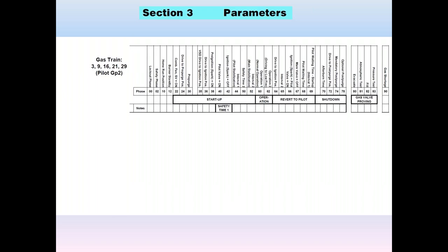In these sequence diagrams, we show all the phases in a row. In red, you see standby and beginning phases coming out of phase 12. In orange, you see the pre-purge phases. Anything in the 40s are the pilots, 50s are main light-off, 60s are all modulation including the revert-to-pilot feature, and 70s are shutdowns. If you invoke gas valve proving, those are phases in the 80s. A low gas pressure situation comes up as phase 90, which is a low gas routine.